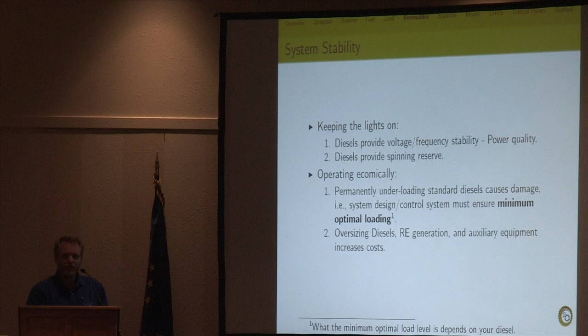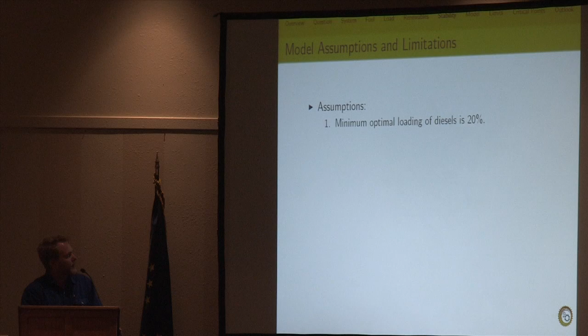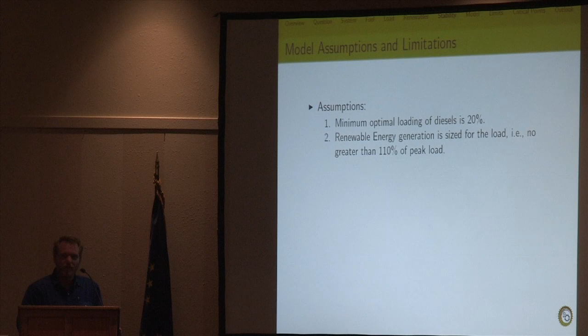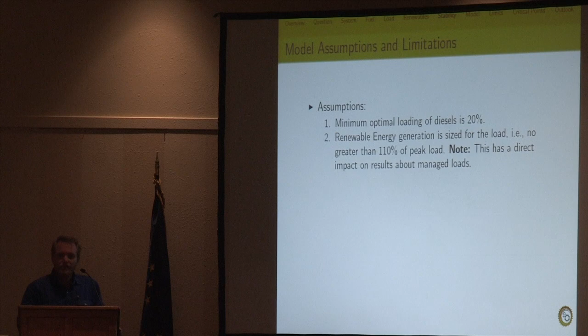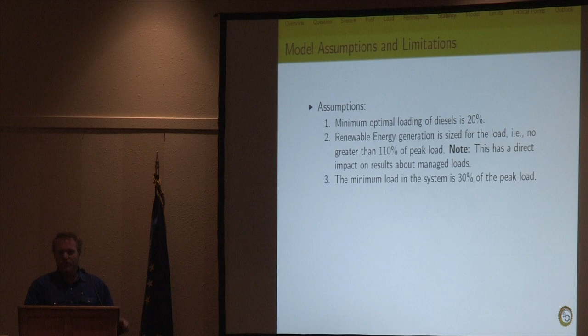So we looked at what can be done under certain assumptions and certain control regimes. Our assumptions are that our diesels here cannot be loaded lower than 20% for any longer duration, and that the renewable energy resource is sized to the load and not just oversized several 100%. Meaning if you have a village that has an average demand of 500 kilowatts or peak demand even, then you wouldn't go much larger than that on your renewable resource. Else you're not looking at the economics right, I think. The minimum load in the system is 30% of the peak load, meaning the load variation doesn't go from 0 to some maximum load, but there's always some demand in the system.